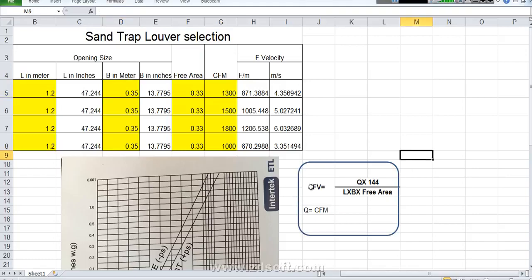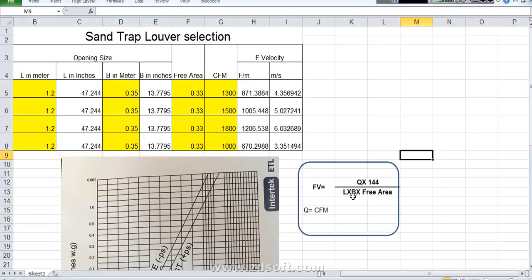This is the equation which we are using for face velocity. FV means face velocity. Face velocity is equal to quantity of air times 144 divided by length times breadth times free area.